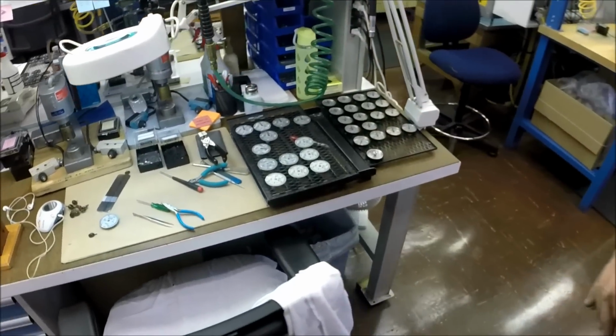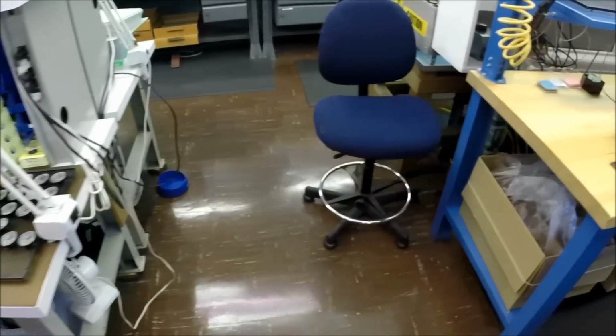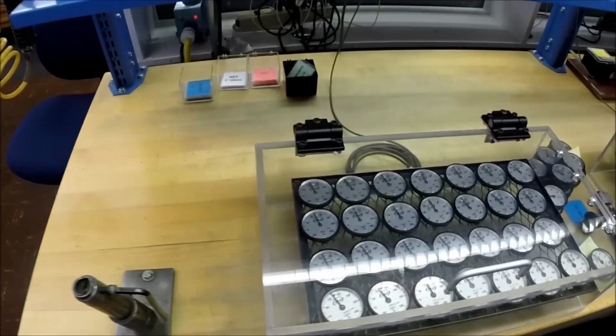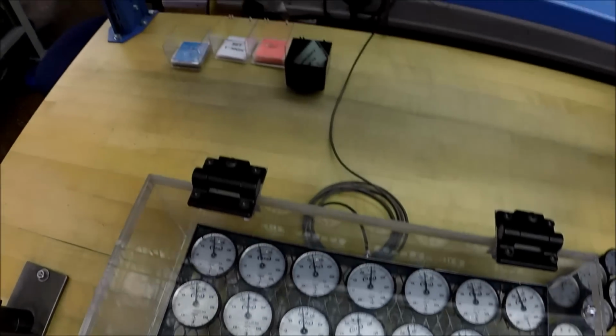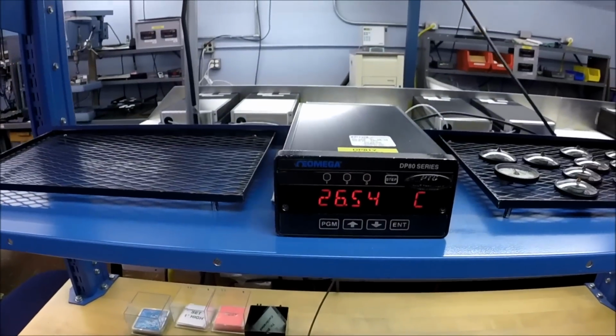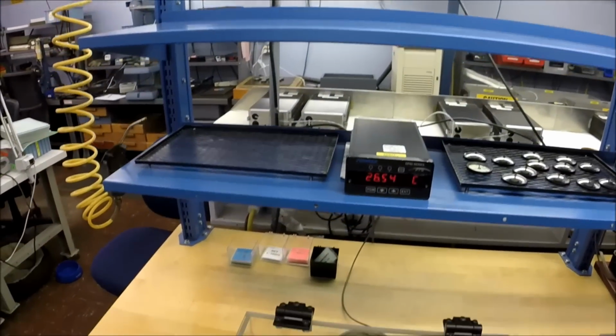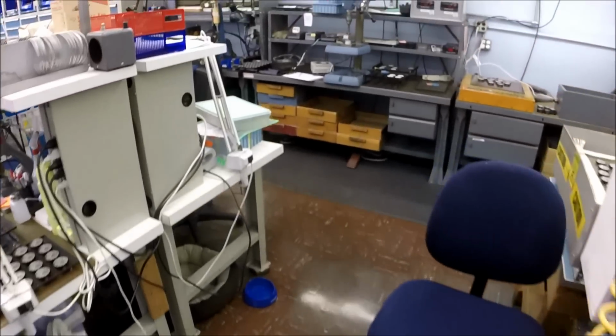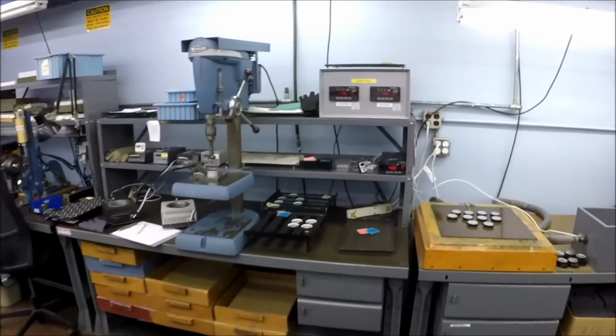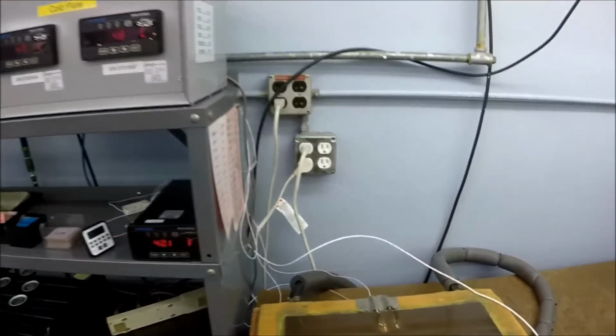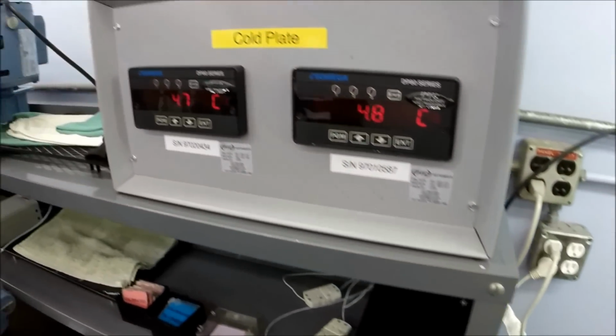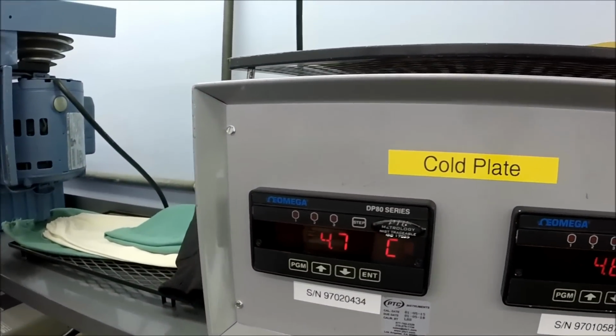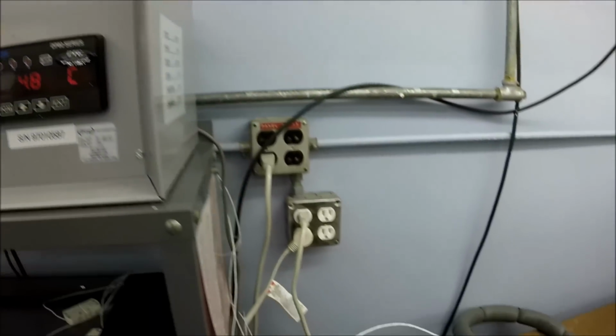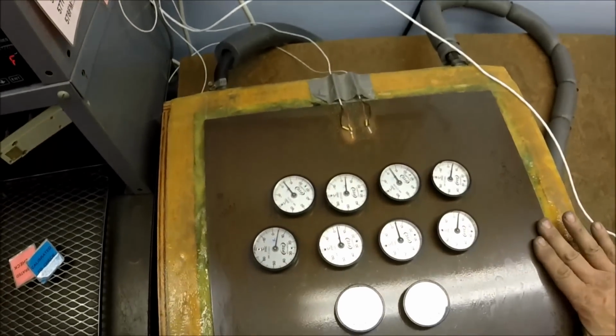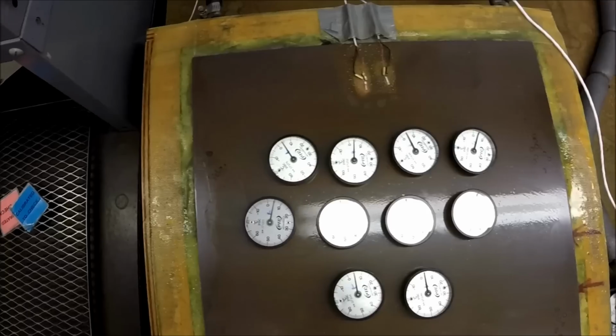We then set them at ambient, which is happening here. This is the preliminary adjustment. Then we will check them at various temperatures. We can check them on a refrigerated plate. This is right now running at about 4 or 5 degrees centigrade. It's cool, you can see the condensation on the plate. That's a 2-inch thick copper plate with embedded cooling tubes in it.